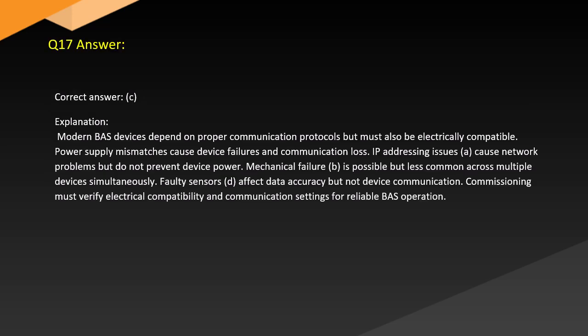Answer. Correct answer. C. Explanation. Modern BAS devices depend on proper communication protocols, but must also be electrically compatible. Power supply mismatches cause device failures and communication loss. IP addressing issues, A, cause network problems, but do not prevent device power. Mechanical failure, B, is possible but less common across multiple devices simultaneously. Faulty sensors, D, affect data accuracy but not device communication. Commissioning must verify electrical compatibility and communication settings for reliable BAS operation.